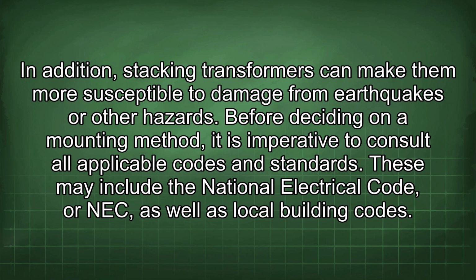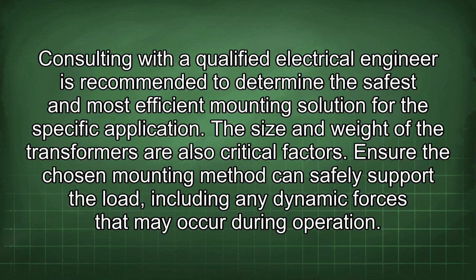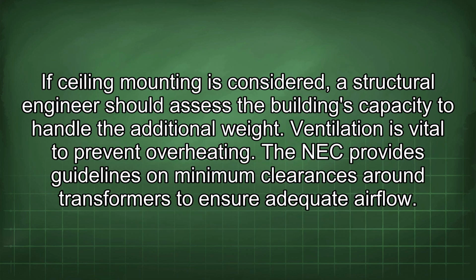Before deciding on a mounting method, it is imperative to consult all applicable codes and standards. These may include the National Electrical Code, or NEC, as well as local building codes. Consulting with a qualified electrical engineer is recommended to determine the safest and most efficient mounting solution for the specific application. The size and weight of the transformers are also critical factors. Ensure the chosen mounting method can safely support the load, including any dynamic forces that may occur during operation. If ceiling mounting is considered, a structural engineer should assess the building's capacity to handle the additional weight.